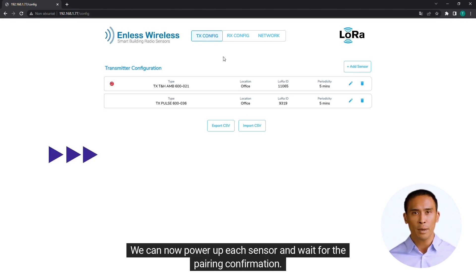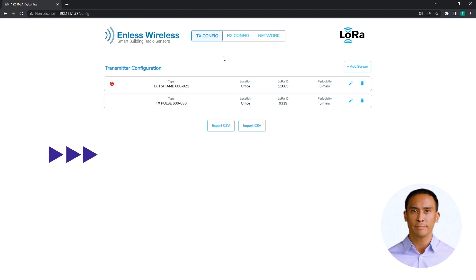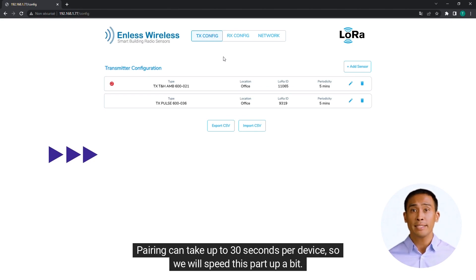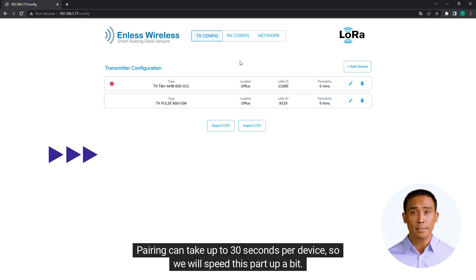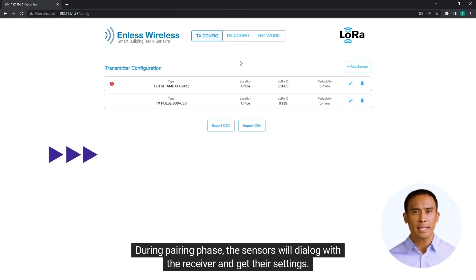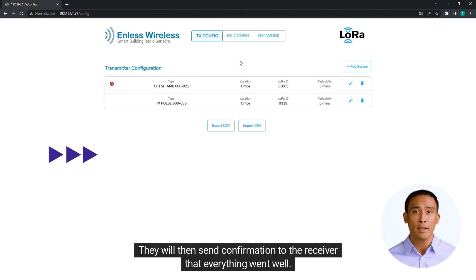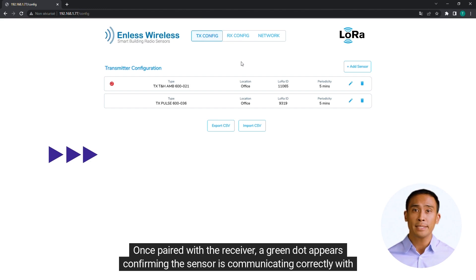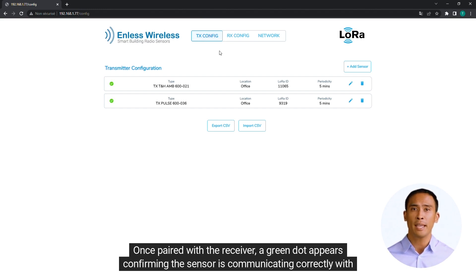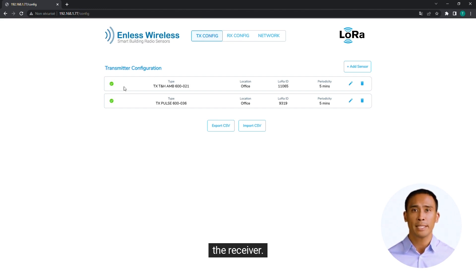We can now power up each sensor and wait for the pairing confirmation. Pairing can take up to 30 seconds per device, so we will speed this part up a bit. During the pairing phase, the sensors will dialogue with the receiver and get their settings. They will then send confirmation to the receiver that everything went well. Once paired with the receiver, a green dot appears confirming the sensor is communicating correctly.